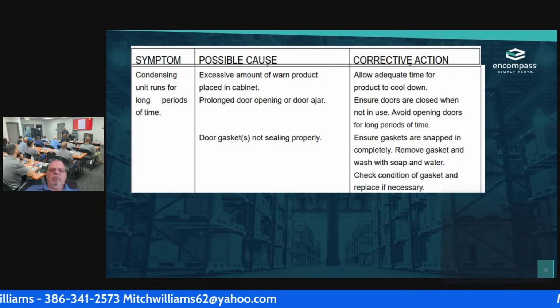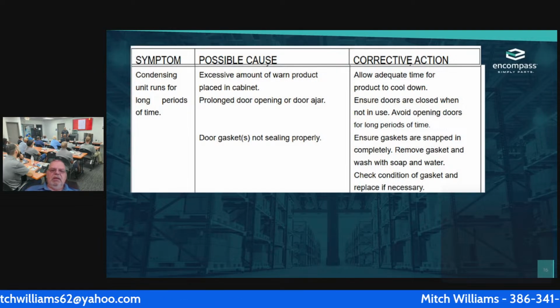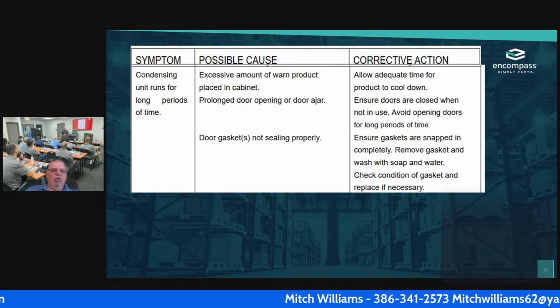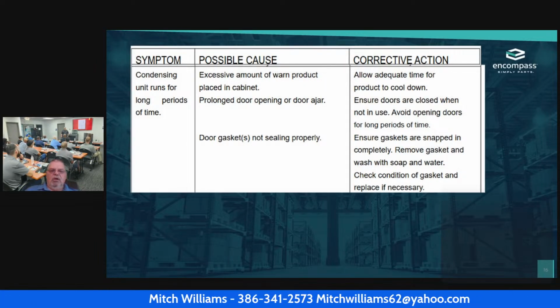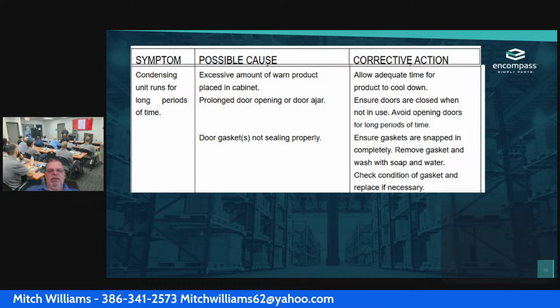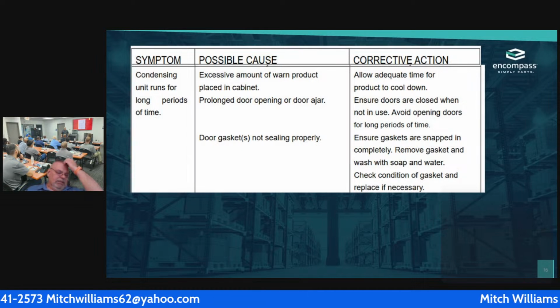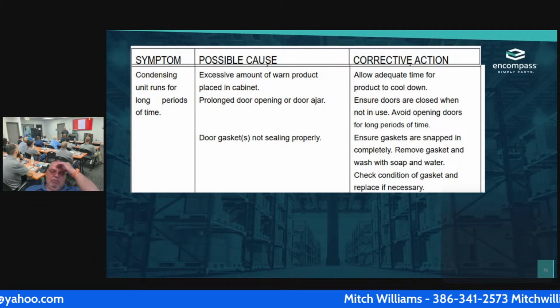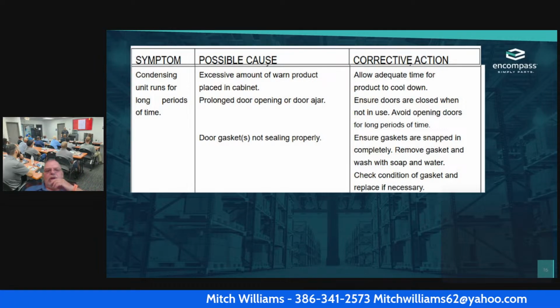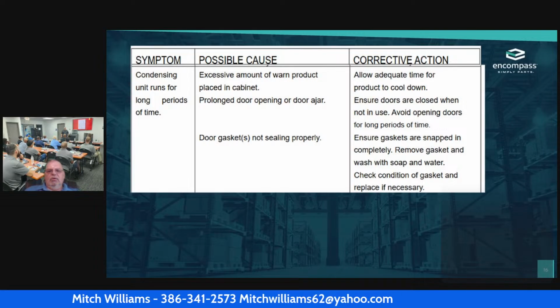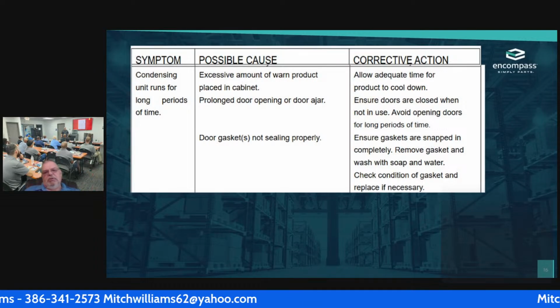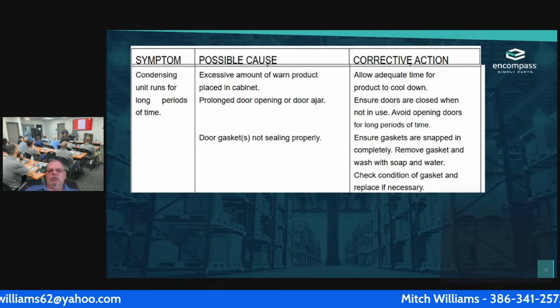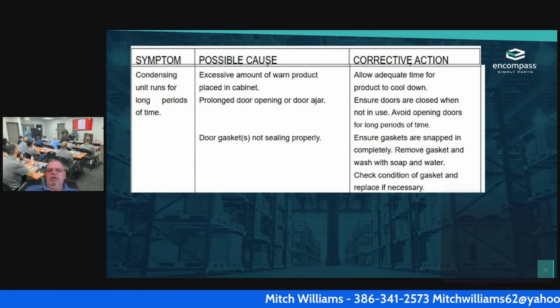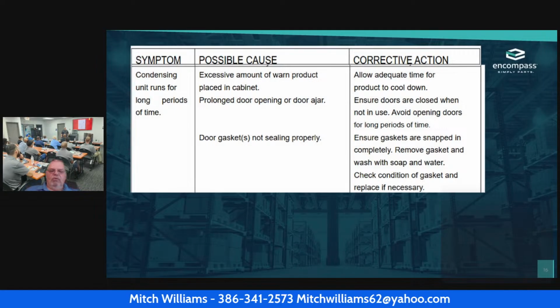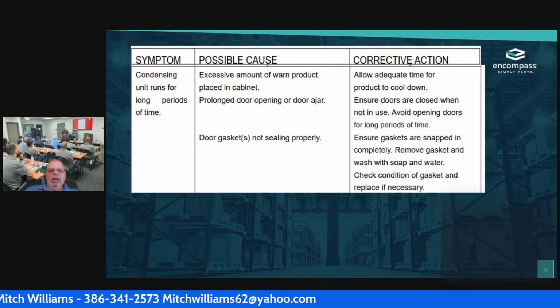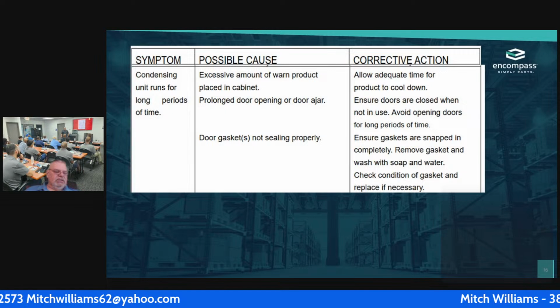Okay. One of the other problems that can happen is that the door has been open for too long a period, or that somebody has gone in and left the door ajar. Like I said, this unit has a locking feature at the back, and that's a good thing. But if somebody just leaves it open, of course, all that cool air is coming right out. So you just ensure the doors are closed whenever they're not in use, and avoid opening the door for long periods of time. And then the other thing that it could be is the door gasket's not sealing properly.